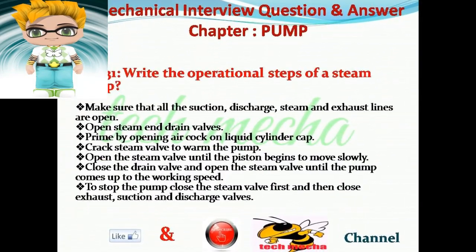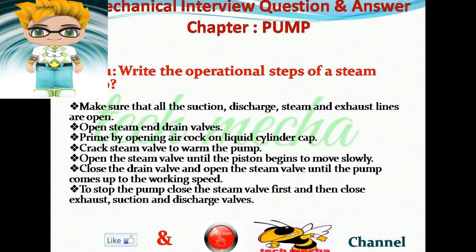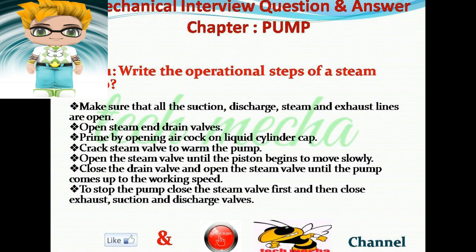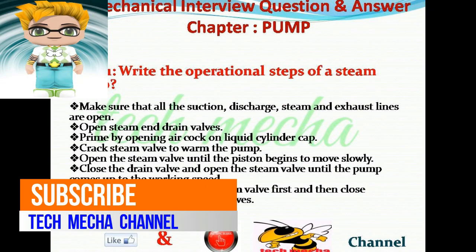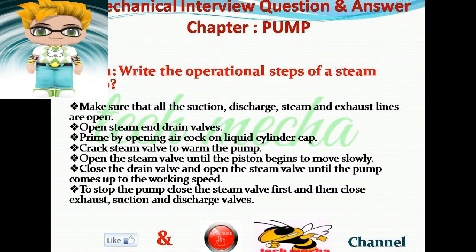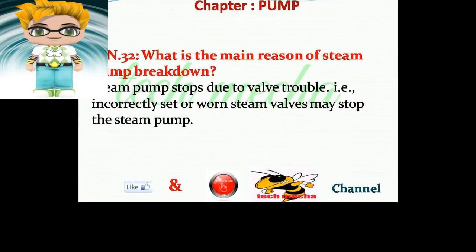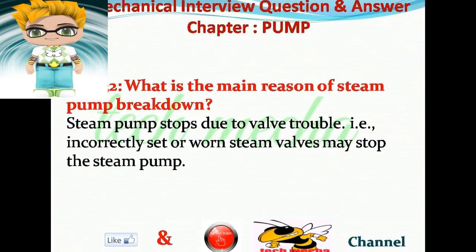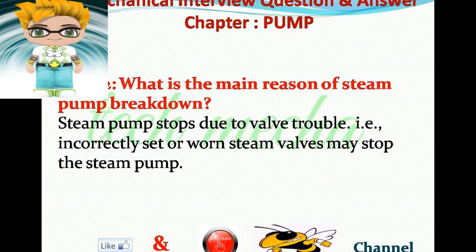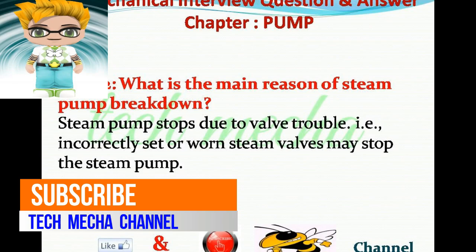Question number 31: Write the operational steps of a steam pump. Answer: Make sure all suction, discharge, steam, and exhaust lines are open. Open steam and drain valves. Prime by opening the air cock on the liquid cylinder cap. Crack the steam valve to warm the pump. Open the steam valve until the piston begins to move slowly. Close the drain valve and open the steam valve until the pump comes up to working speed. Question number 32: What is the main reason for steam pump breakdown? Answer: Steam pump stops due to valve trouble — incorrectly set or worn steam valves may stop the steam pump.